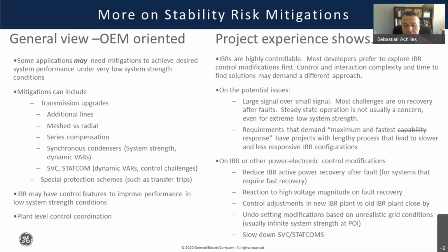I'm going to skip the next one, and then the other one that is coming up very often is the slowdown of SVCs and Statcoms that already exist. It has been the approach in the SVC and Statcom industry to tune them very fast, like 50 millisecond voltage regulator response times, with the idea that the systems get stronger and stronger. So that's the best you can do. But now, because the systems actually get weaker and weaker, many system operators are finding themselves having to retune SVCs and Statcoms every couple of wind plants or solar plants that they connect. They have to retune them and slow them down because they're too fast for the new system strength levels.